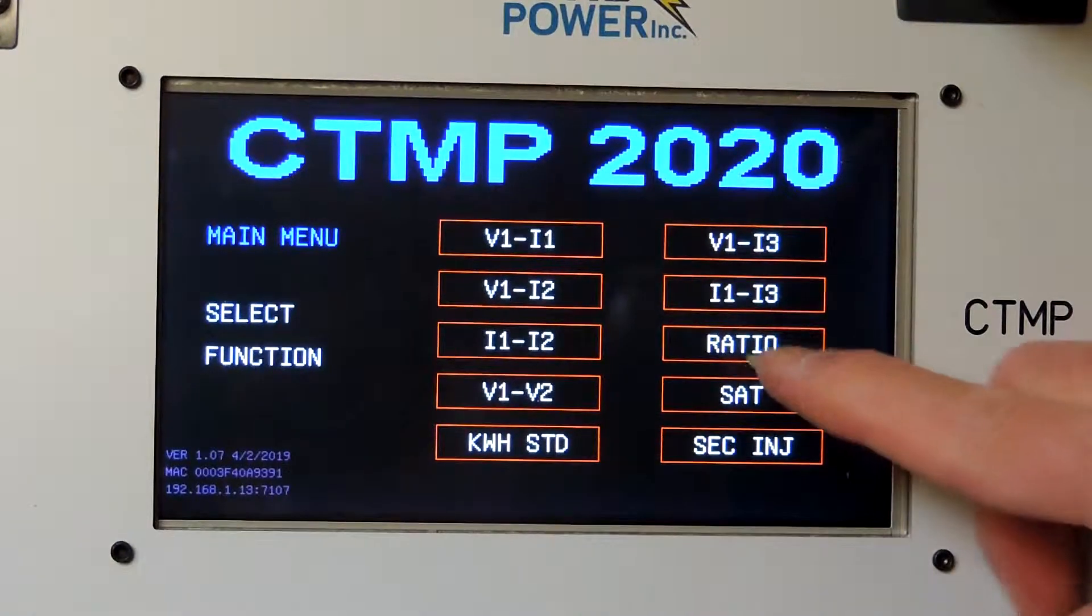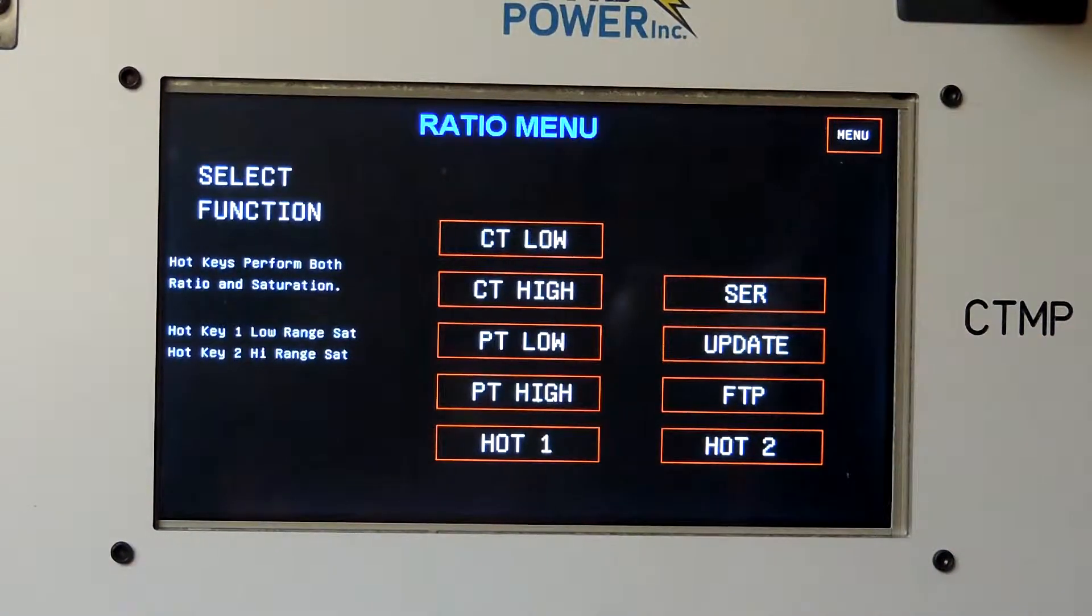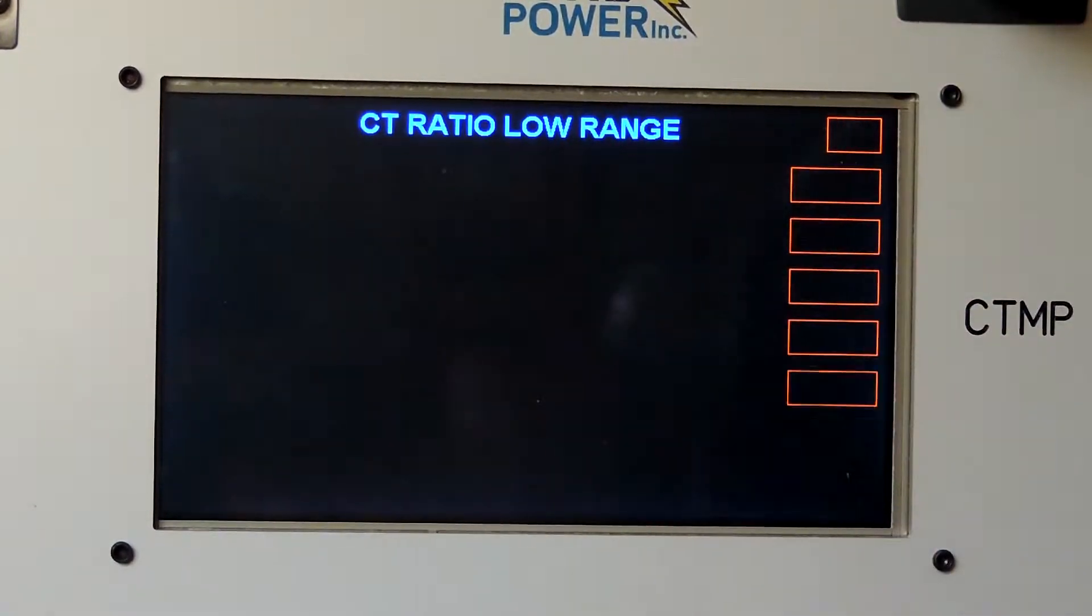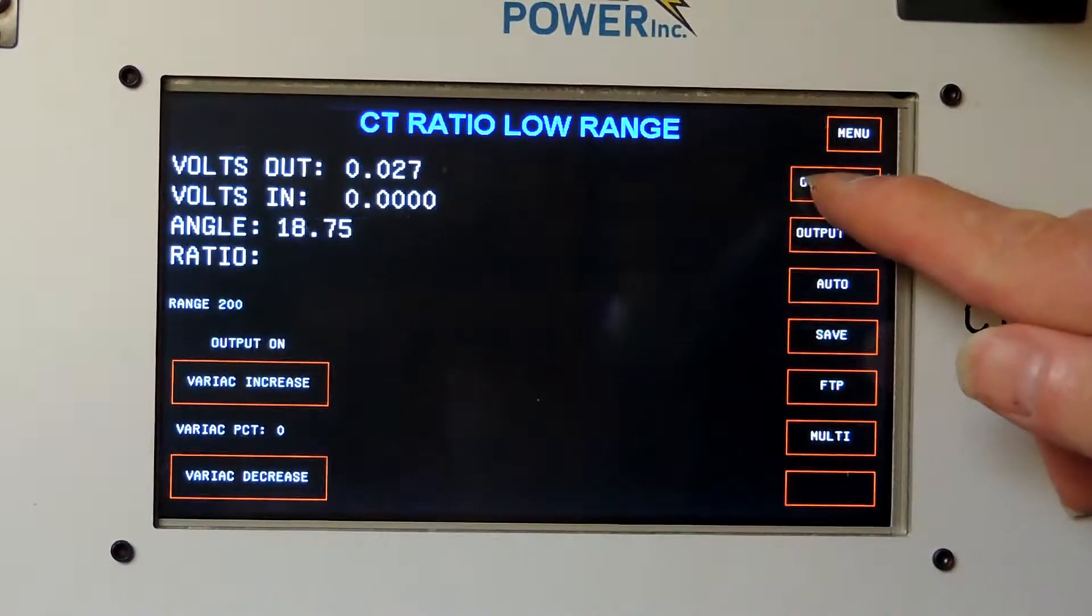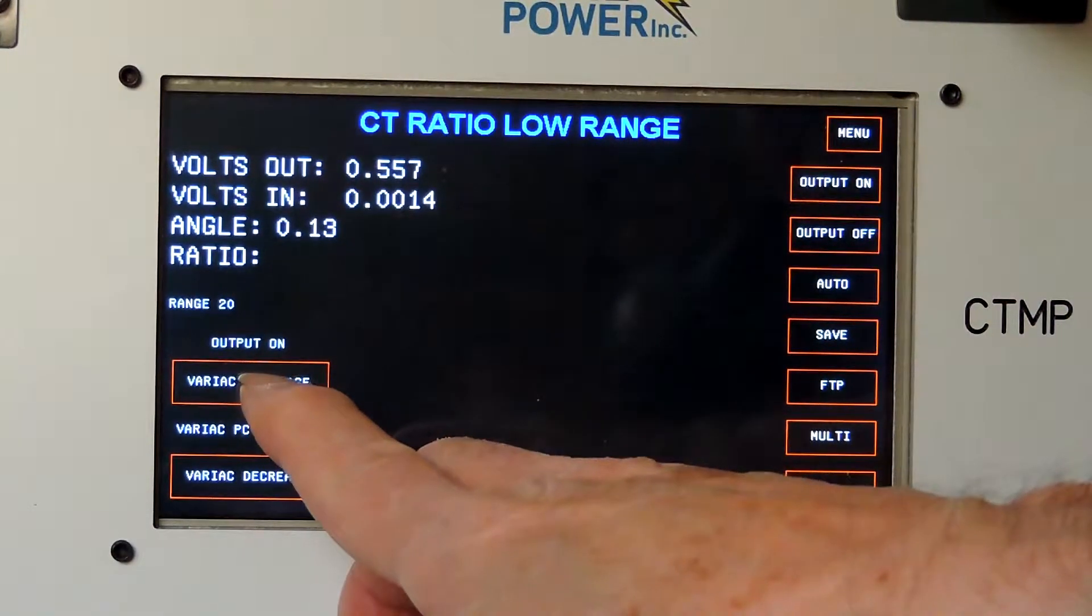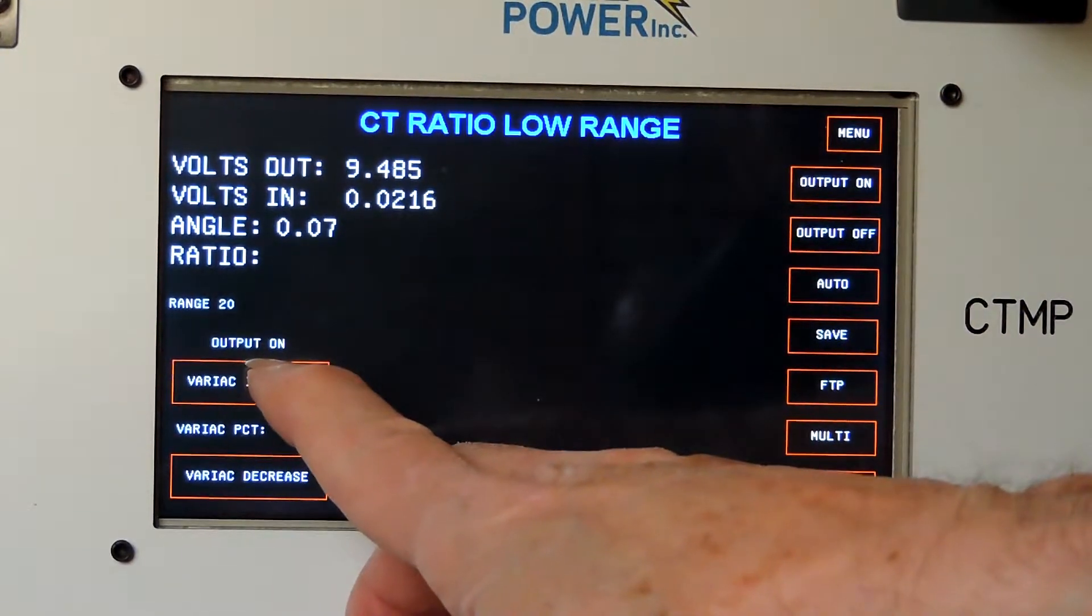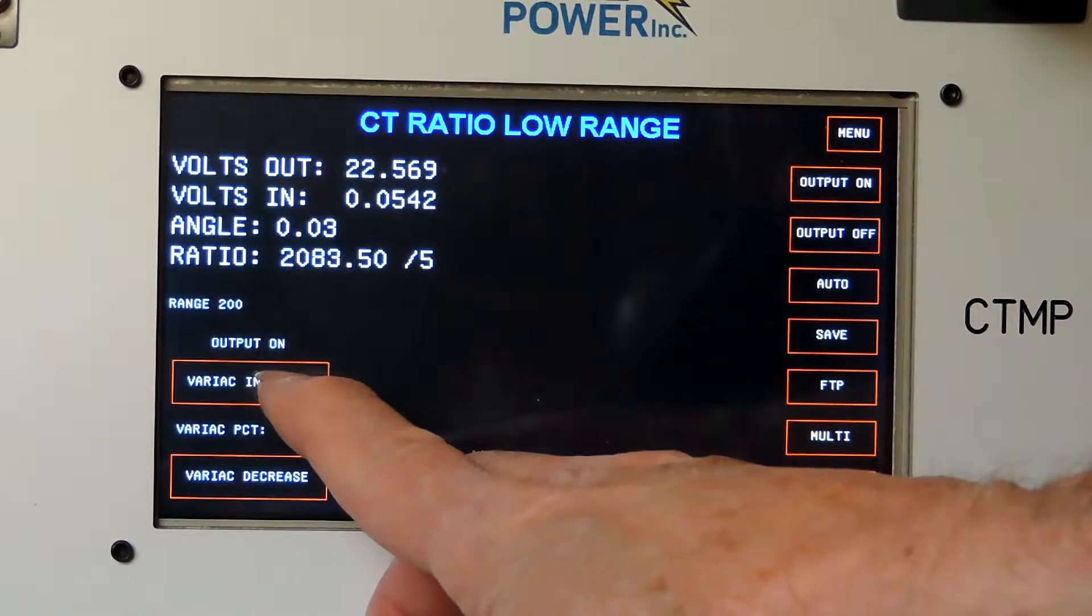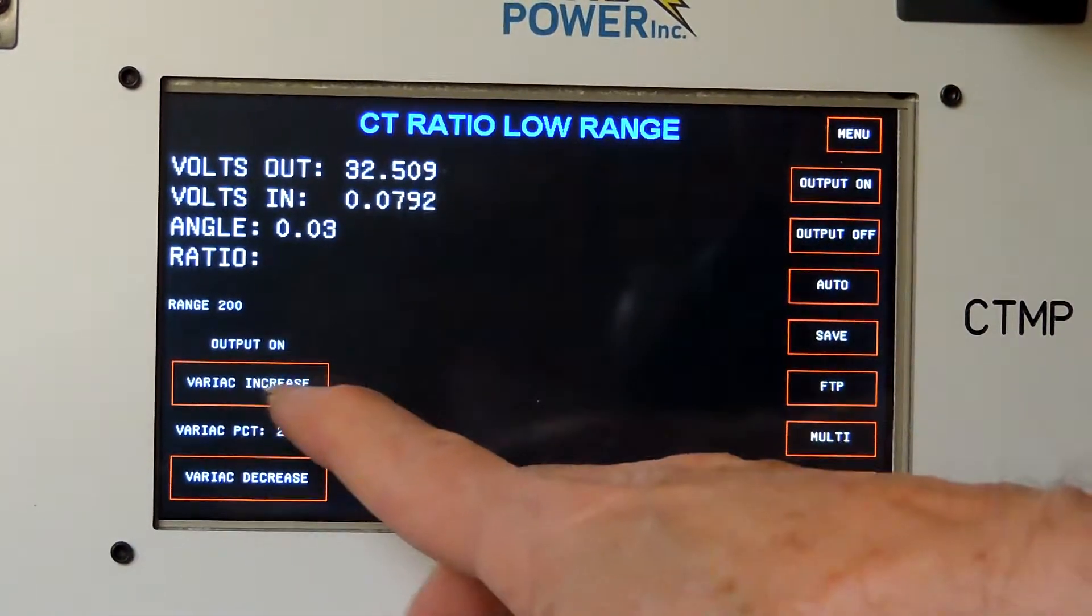So the first thing I'm going to do is a ratio test. I'm going to select ratio, and it's below 10,000 to 5, so I'm going to select CT low. That's most of what you'll use. I'm going to turn the output on and I'm going to increase the variac until I get a single turn primary voltage to about 0.1 volts. You don't need that much, but that is the usual target.